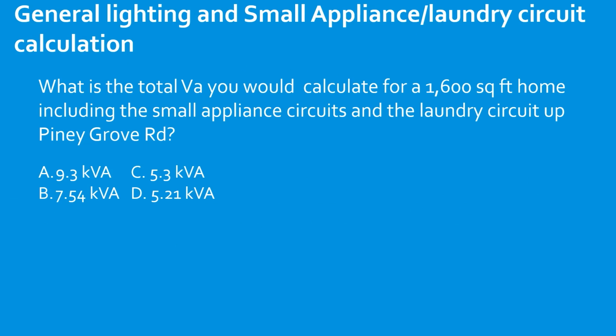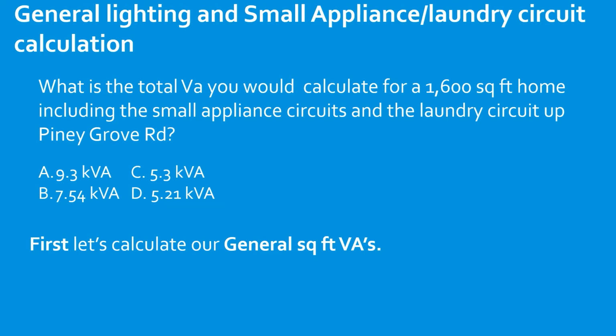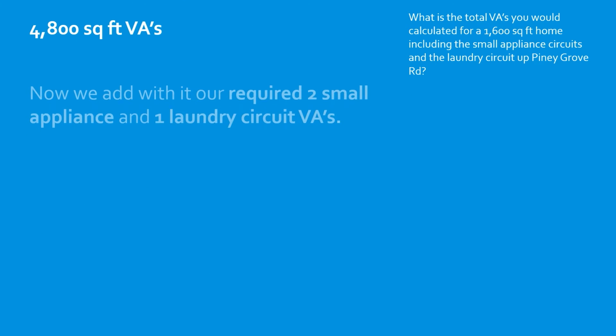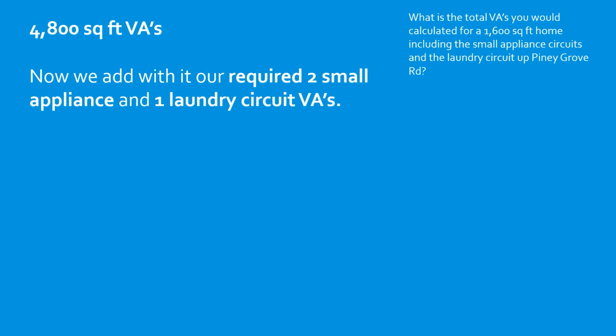Let's get to it. What is the total VA you would calculate for a 1,600 square foot home, including the small appliance circuits and the laundry circuit? The first thing we're going to do is calculate our general square foot VAs. We take our 1,600 square feet and multiply by 3 VAs per square foot, which gives us 4,800 VAs. Now we add it to our required 2 small appliance and 1 laundry circuit VAs. Remember that we count 1,500 for each, so we take 3 multiplied by 1,500, which gives us 4,500 VAs.